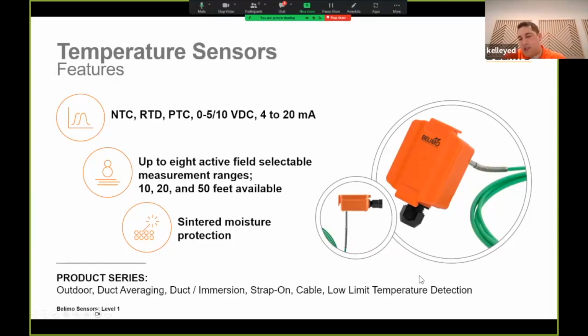One thing to note, so the images you guys are looking at, we've got this green capillary here. That's one of our averaging temperature sensors. Typically averaging sensors go cross-sectionally across a duct because you want the full picture of the temperature within the entire duct space. The larger the duct gets, you have air stratification. So hot air rises, of course, cold air drops. The cool thing with Belimo's green capillary here, it's one continuous sensing element. So anywhere where this green capillary is, it's measuring a true average, as we call it, anywhere it's installed in the duct itself.